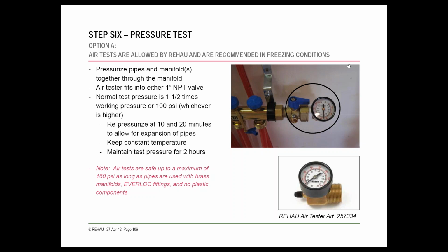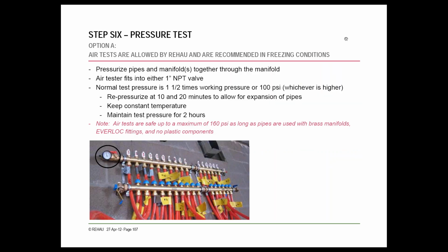All right. As far as testing, air testing is permitted by REHAU and most other manufacturers. It's a great way to do it, especially if it's in freezing temperatures. You want to test it ahead of time, of course, and then you also want to keep it pressurized during the pour if you're doing a wet application.